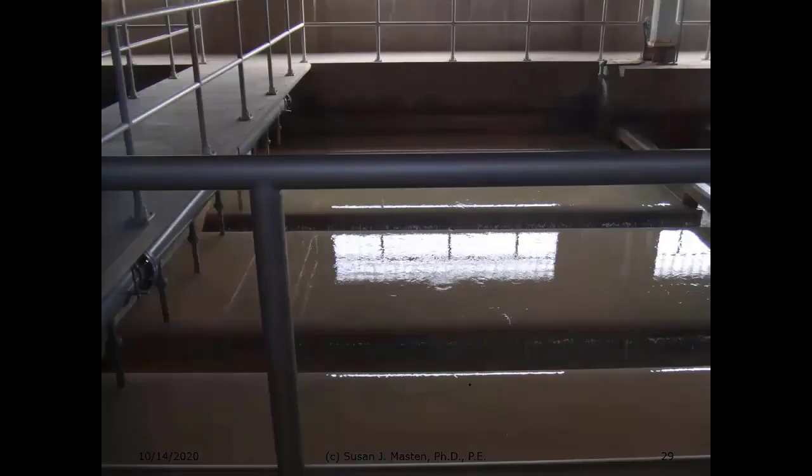This is a photo from the Dye plant. This is during backwashing. So the water is flowing upward through the filter bed, so it's fluidizing the bed, and that water is flowing over the sides into the top of the wash trough and then to the gullet. And then in this case, this is a groundwater plant.